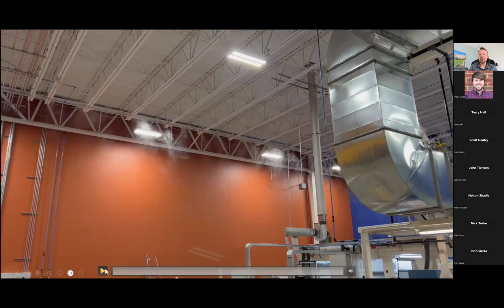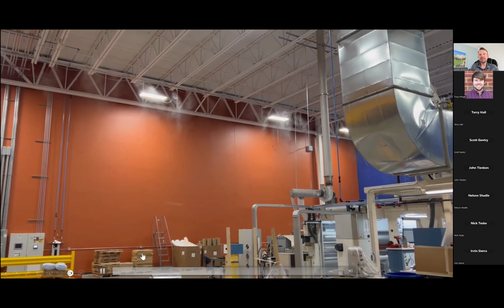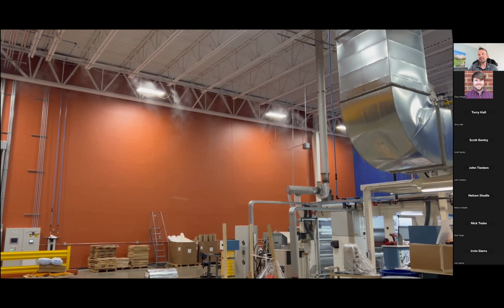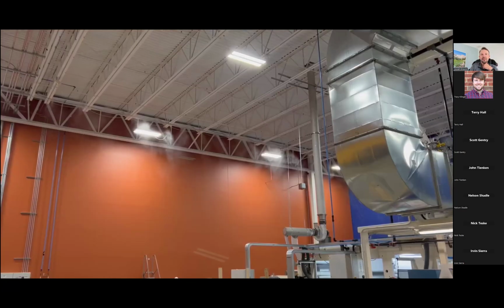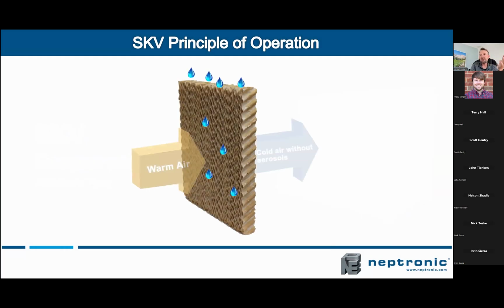just what it looks like when you have a call for humidity, it's just a little bit of mist coming out of nozzles. The nozzles aren't above any equipment or anything, in case there was a leak or something in the plumbing. Just something like that is adding enough moisture to keep their indoor relative humidity, and they're overcoming the cooling effect. This is in Wisconsin, so they're just using gas heat or some other kind of heat to overcome that cooling effect.